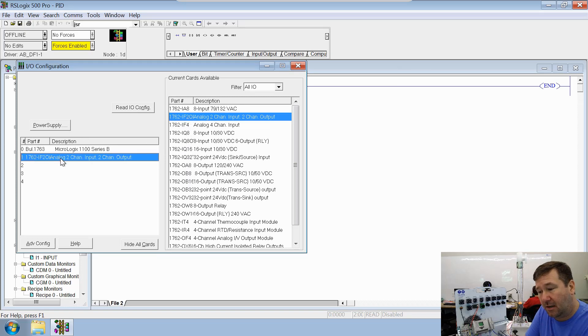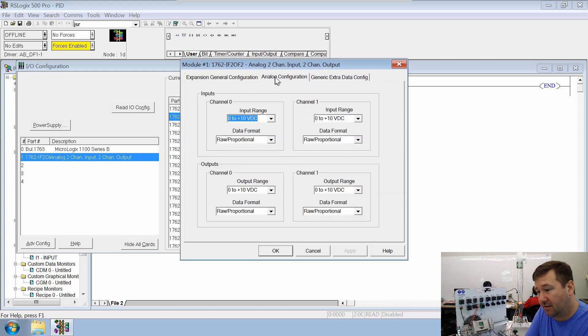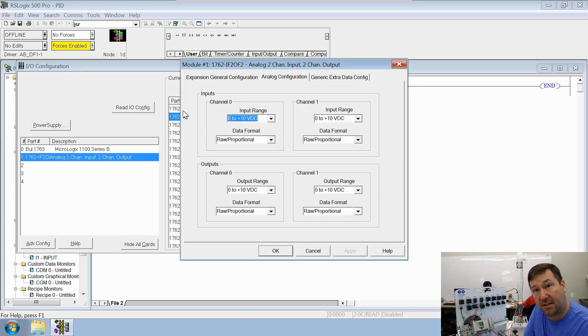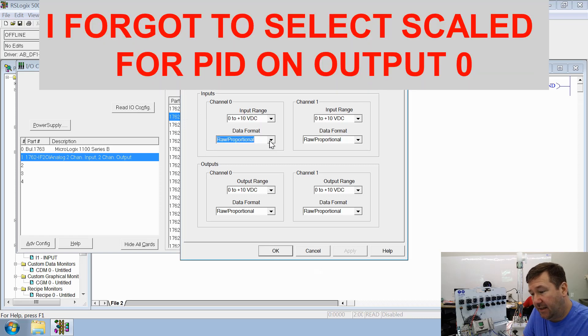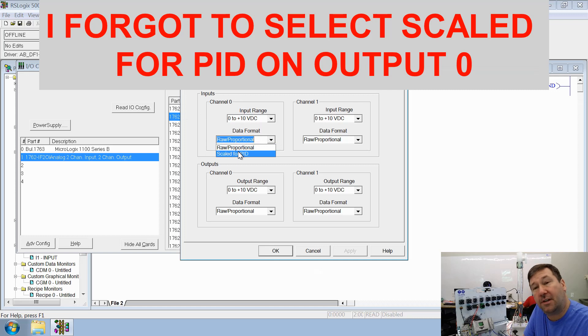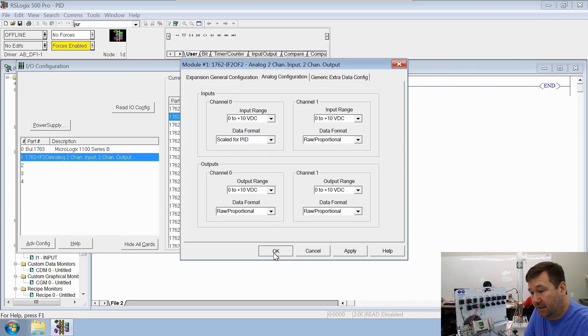And then let's open it up just to double check its analog configuration. If we go over here to analog configuration, it does default to zero to 10 volt DC, which is exactly what we want. And then you can either use raw proportional, or you can use scaled for PID. And since we're going to be doing a PID, let's go ahead and scale it for that. Click OK.